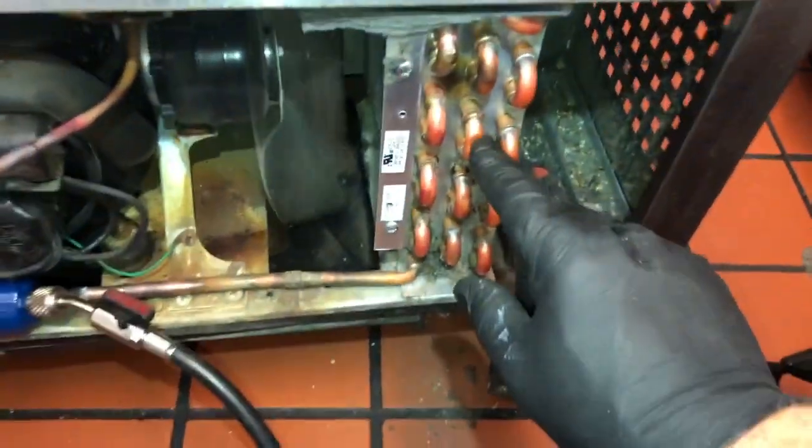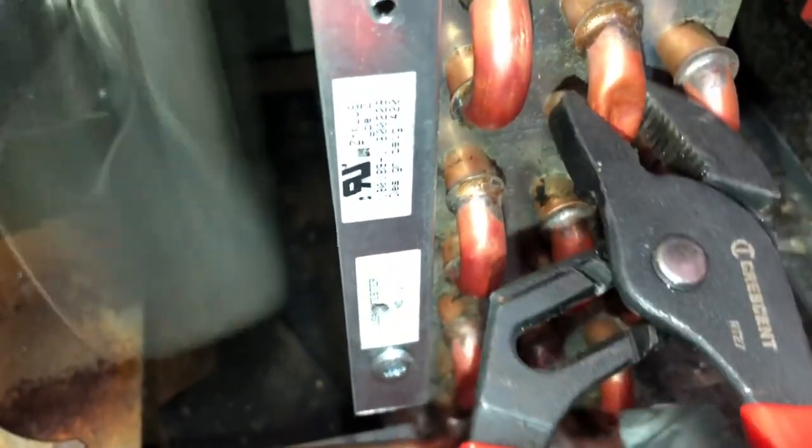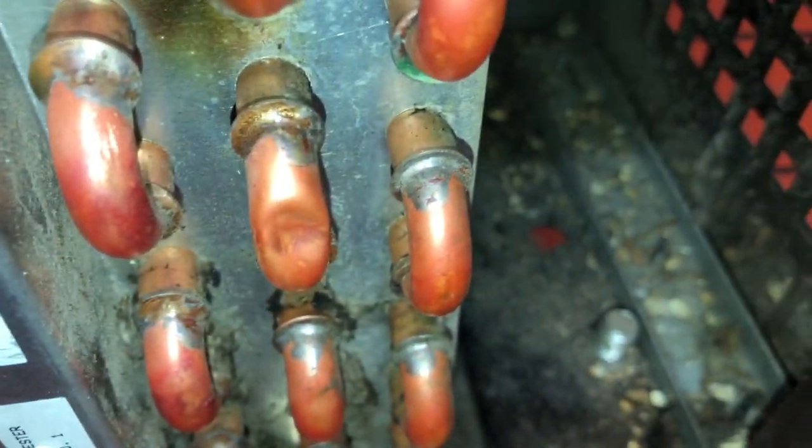This one almost got a hole in it and was squished in. I just took the channel off and made it round again as much as I could, because the copper is so thin, but I'm getting through there. Installed the access fitting and the dryer, then found out the thermostat was the actual reason it was jacked up.